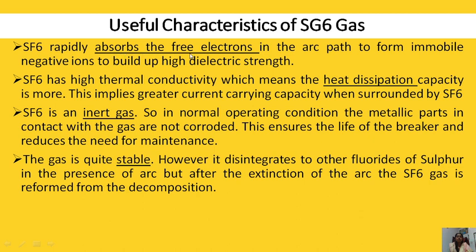SF6 gas absorbs the free electrons in the arc path to form immobile negative ions, to build up high dielectric strength. When contacts get separated, there is a formation of arc, which means there are more free electrons. But the property of SF6 gas is that it absorbs the free electrons due to its electronegativity property. That is why the build-up of high dielectric strength is faster.